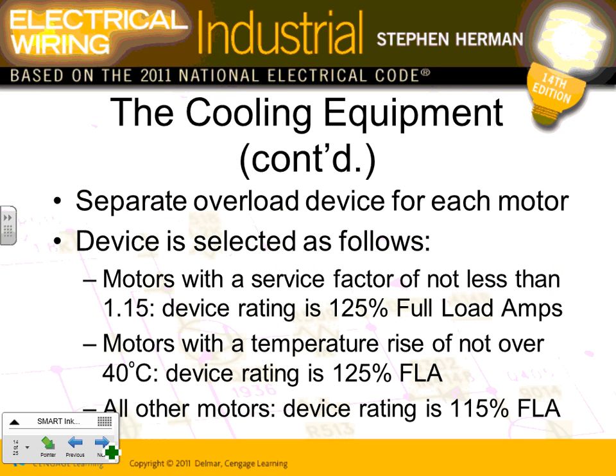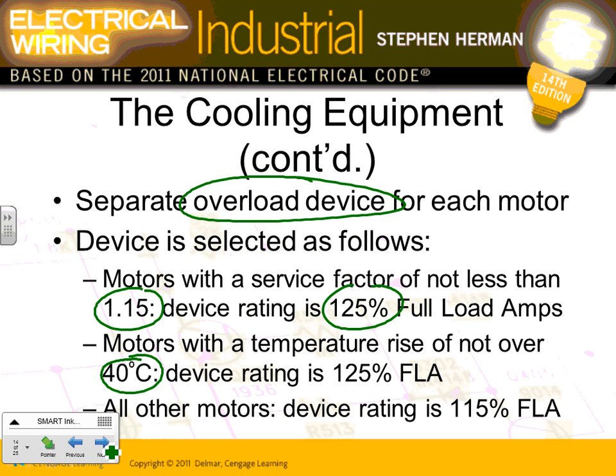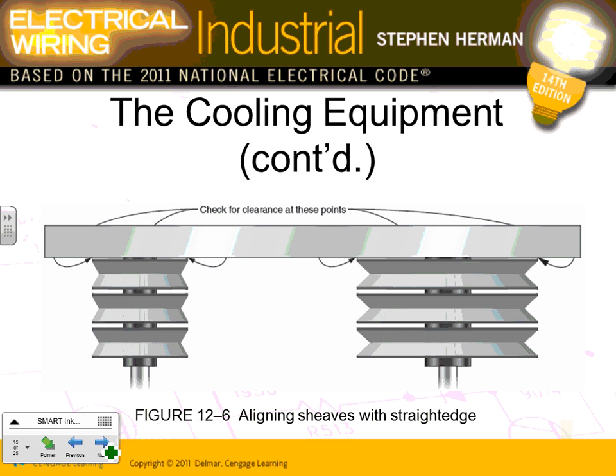Separate overload device. This talks about the overload, guys. We sized a lot of these before. It just tells you the rules for the overload. Very quick review: if your service factor is 1.15 or larger, 125%. If temperature rise is less than 40, 125%. All other cases is what? 115%. I wish you guys remembered that when we did the test. Almost all of you remember, but one did not. Remember how to size the overload. I know we sized them, so I'm going to skip that one.